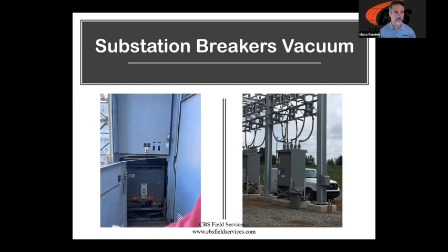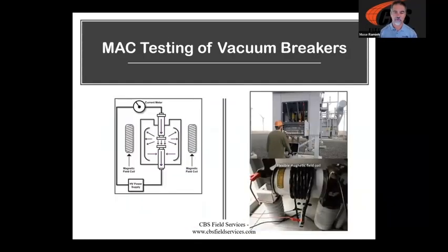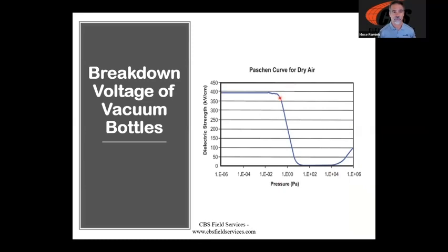Vacuum breakers. Once again, whether they're a substation type or metal clad, there's a lot of great testing that we've already talked about, insulation resistance, contact resistance. But how do we know what the condition of the vacuum bottle truly is? And historically, we've done that with an AC over potential test, right? We apply a voltage. If the open breaker does not break down on the voltage test, then we deem it good. But the one thing that we never knew or we couldn't tell is, hey, am I sitting at this point on what's called Paschen's curve, right?